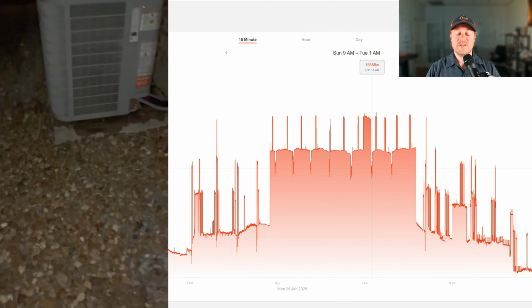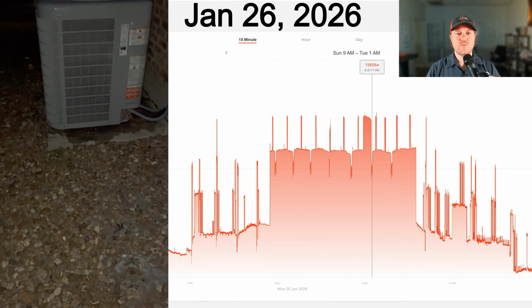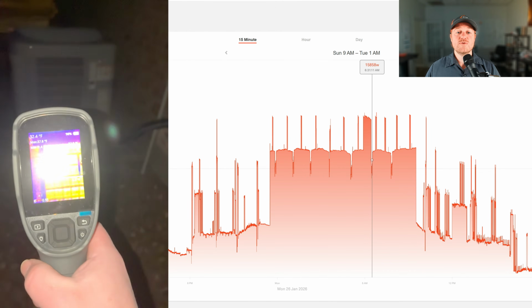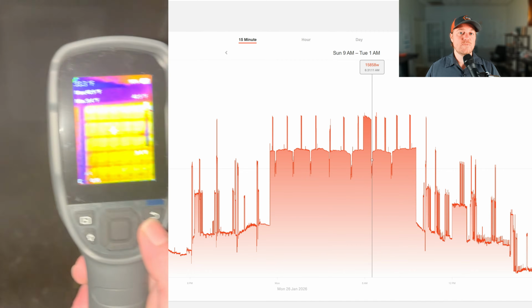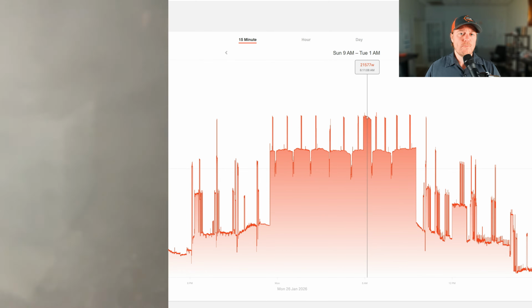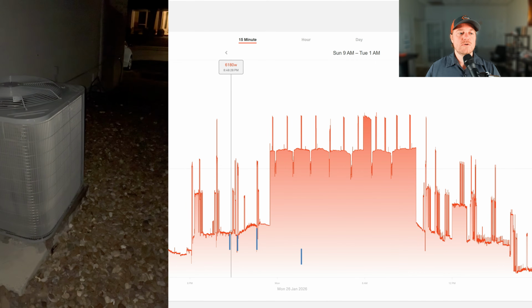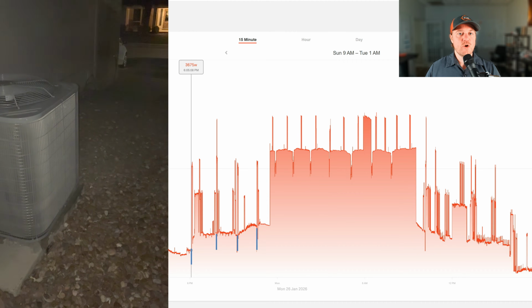Right here, we're looking at a report from my power metering device, and this is showing the data from January the 26th, 2026. Now, this report is showing everything that the house is pulling. For example, this spike right here is the water heater, but we can still use this report to see what our heat pump is doing. Because right here, I can see these little power drops. And that is the system going into defrost mode.